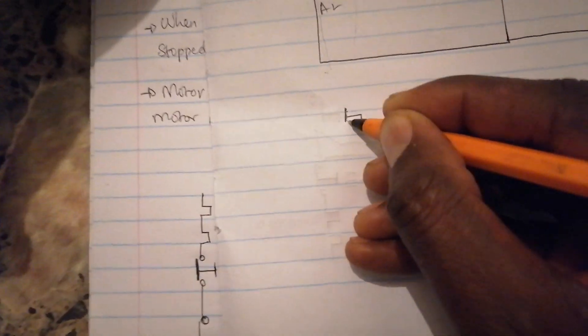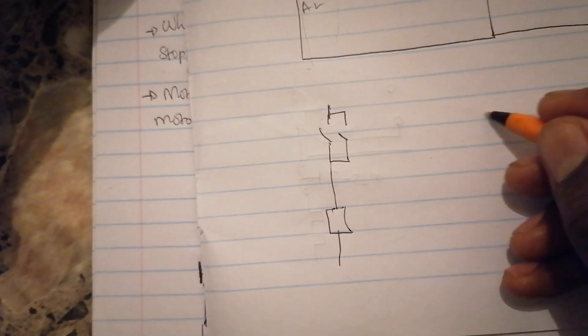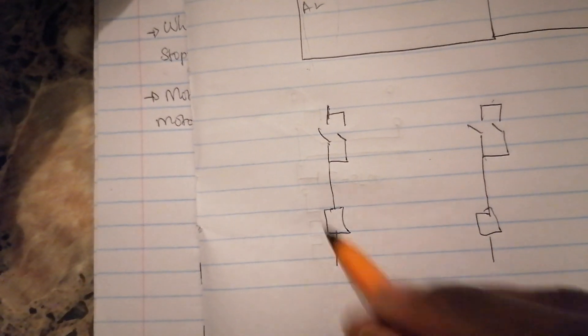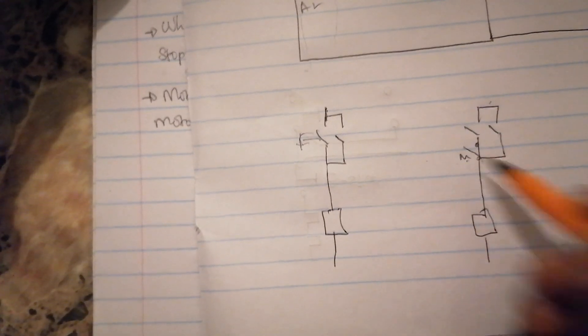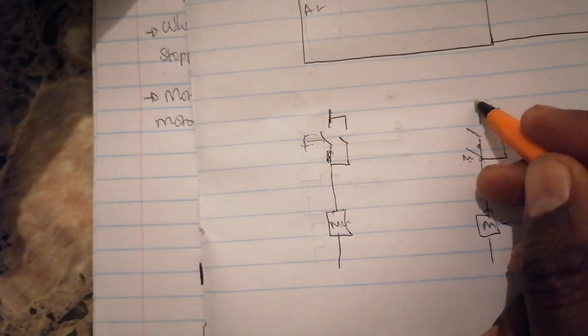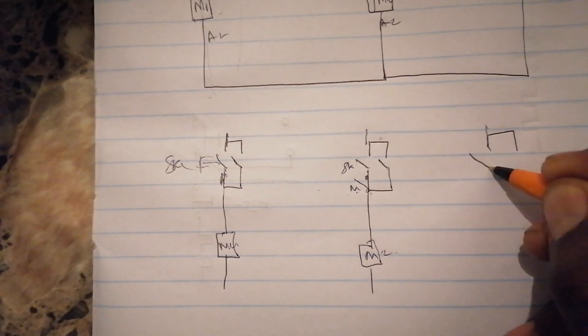So when you start writing your sequence, you can start by writing 2-DOL like this. Then listen to your statement - what does it say. We have motor one and motor two. If they say when motor one starts, motor two cannot be started, that means you have to put them normally closed. If they say motor one cannot be restarted unless motor two is stopped, put them normally closed. Check for another option - this is your start-start configuration and the difference is where you put your interlock.